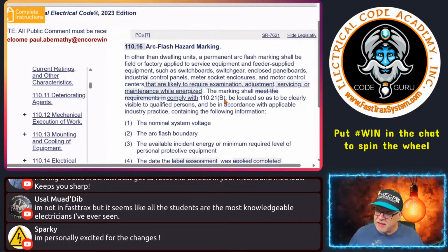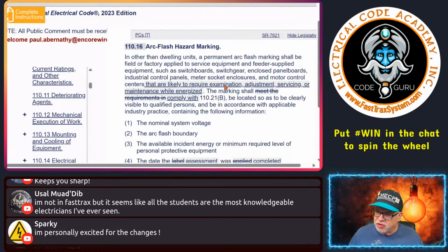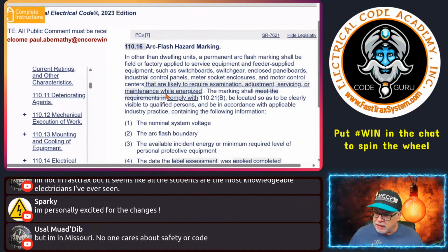Right here they added this element that says that other than dwelling units, a permanent arc flash marking shall be field or factory applied. And here's what they added: it says, and motor control centers that are likely to require examination, adjustment, servicing, or maintenance while energized. So it seems to narrow it down now, requiring this permanent arc flash marking on all of this equipment: switchgear, enclosed panel boards, switchboards, industrial control panels, meter socket enclosures, motor controls, all of them that are likely to require examination, adjustment, servicing, or maintenance while energized.